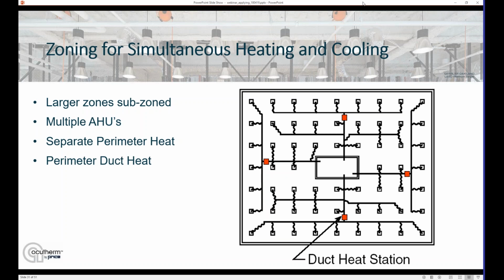Duct heaters, the very classic reheat approach. In this case, we are putting a duct heater on each of the faces of the building, and when that, again, as we spoke earlier, if the north needs heating while the south needs cooling, we can bring the heat on in the north while still running the cooling in the south. Not as energy efficient as some of the other approaches, just because we are doing reheat, but still a very common method today.